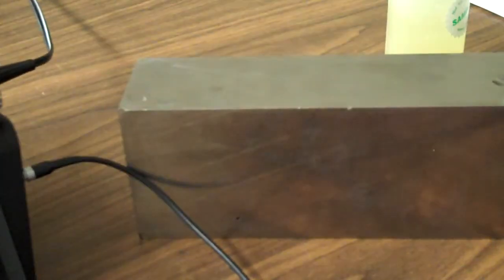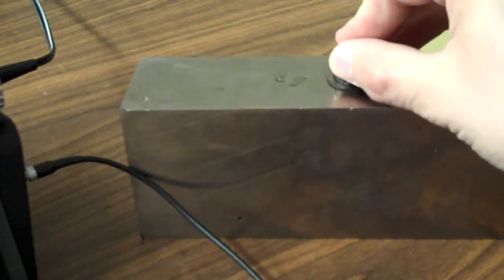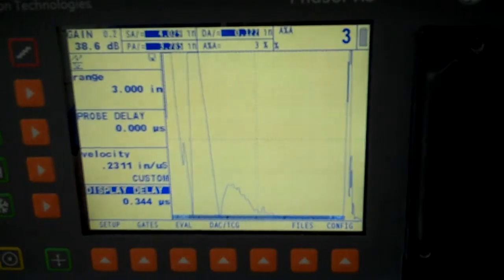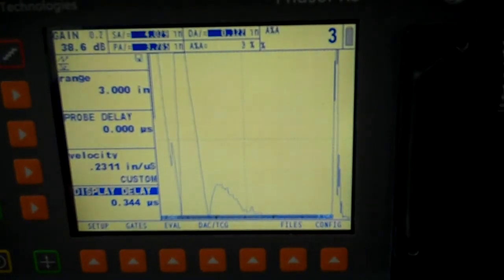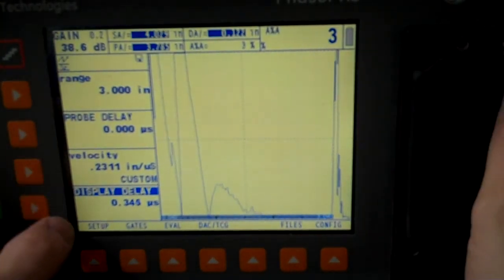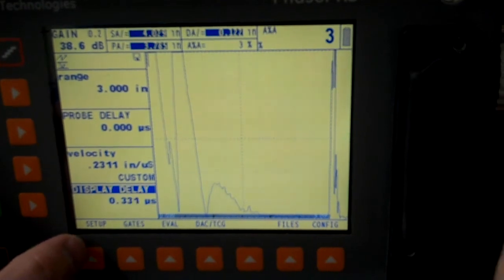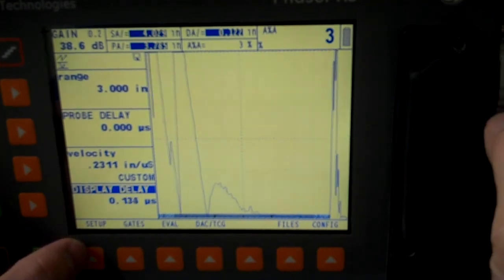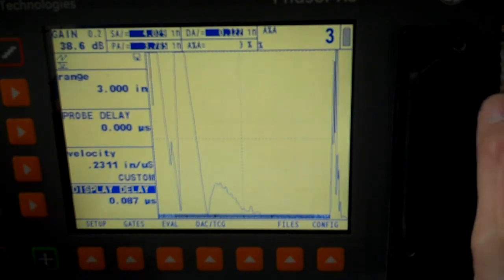So I take the transducer over here to the 3-inch block. There it is on the 3-inch block. See if we can zoom out enough. There's our signal, 3 inches at 100%. It should be right at 100%, which is what we want. I'm just doing a little adjustment here. 3 inches right at 100%. That's where we want it.